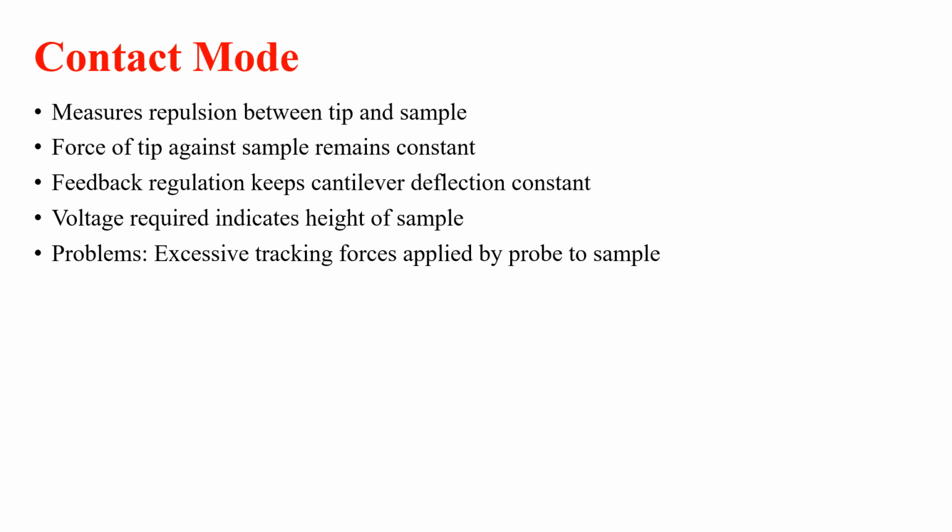So that is the contact type. The voltage required is for indicating the height of the sample. But there is a problem with this contact mode: it has an excessive tracking force applied by the probe to the sample. So there are chances that we can have scratching on the surface, or the tip of the probe can get damaged, so we will not get accuracy. So that is the problem behind contact mode.